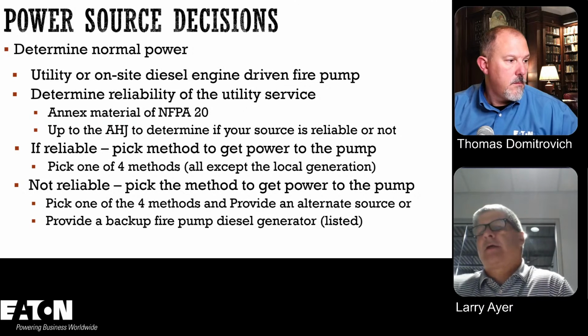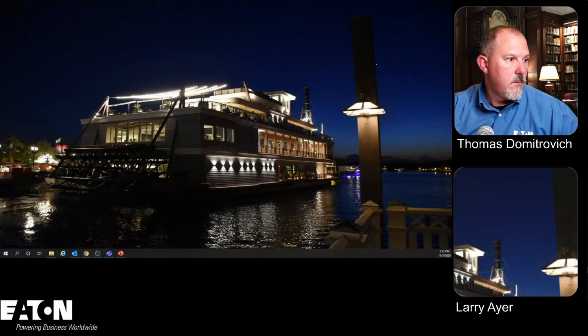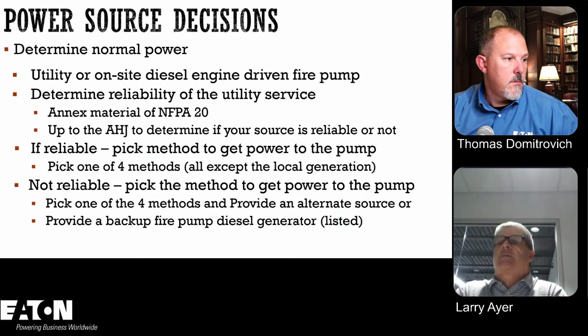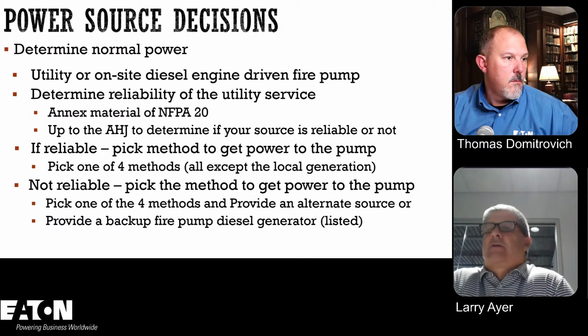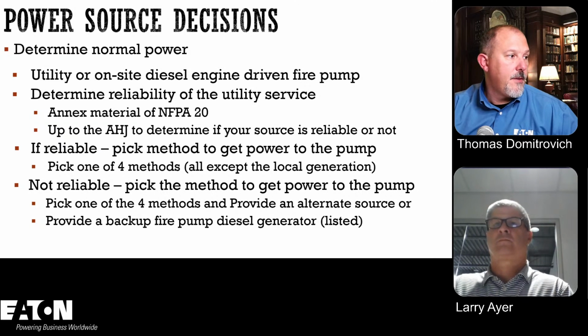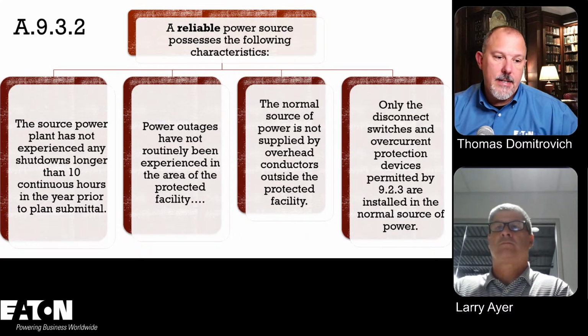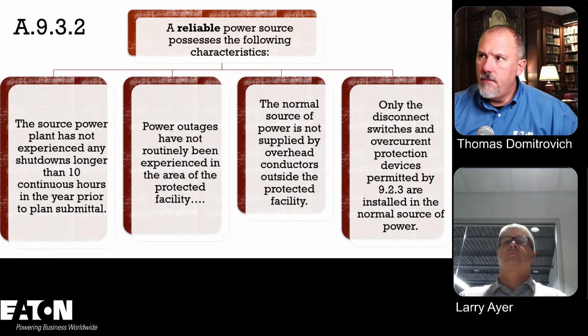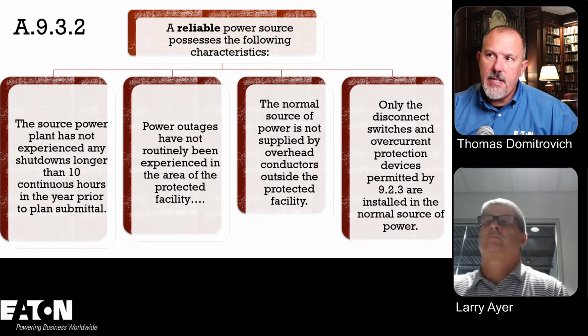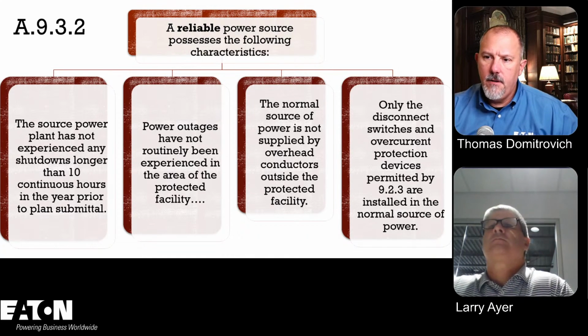In my area, I do not see many diesel-driven fire pumps. I see more or less fire pumps installed by themselves, with either a backup generator or without. Interesting. Okay, so that helps me understand. Now, this next slide is a little busy, and this is out of the annex material. When you see an A in front of those numbers, that's the annex material? Correct.